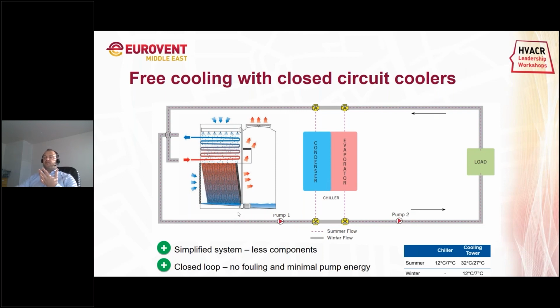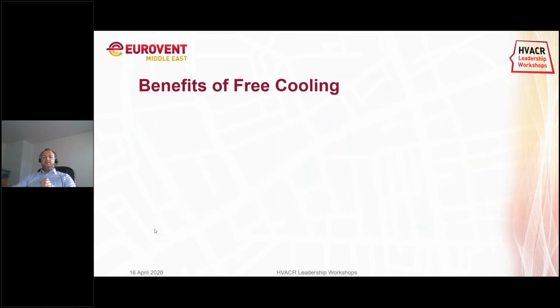We always advise the free cooling with closed circuit coolers because there are some advantages. You have a more simple system and less components. You have the closed loop, so there's no contamination. The air cannot reach the process fluid, so you will have no fouling, and you will also have less pump energy required.